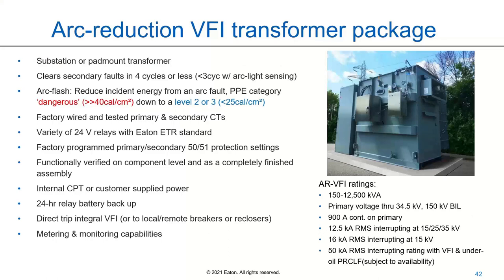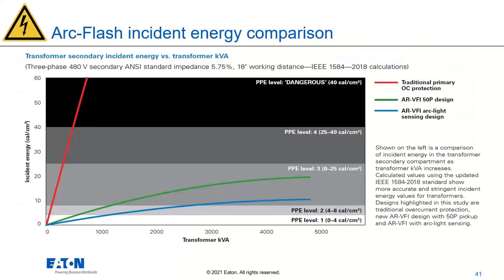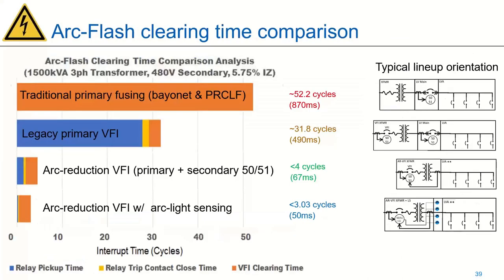Yeah, there are a couple of questions, Sam. One of them seems like it was answered in line with the slides you were doing. Basically, would the transformer primary fuse protection be faster than the recloser? And you showed that it would not. Is that the case in every installation, or is that pretty much standard as far as the lineup or sizing of the fuse? Yeah, you definitely have to take into account the size of the fuse or the recloser settings.